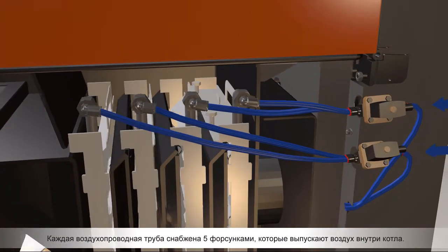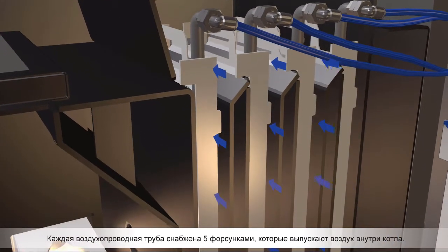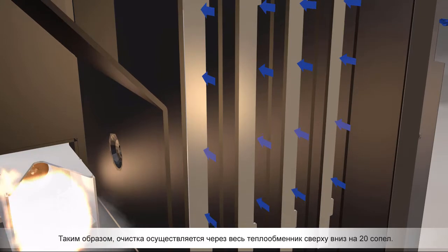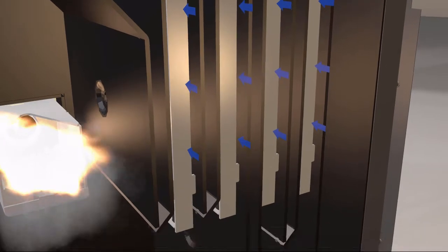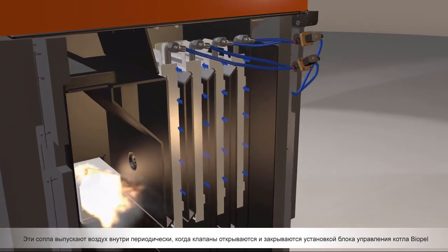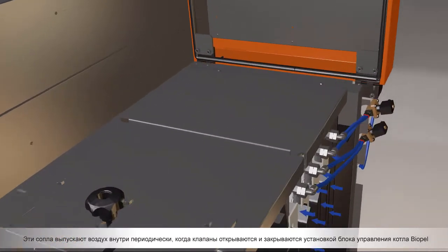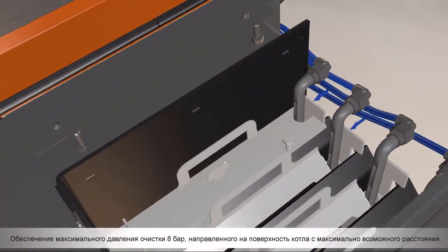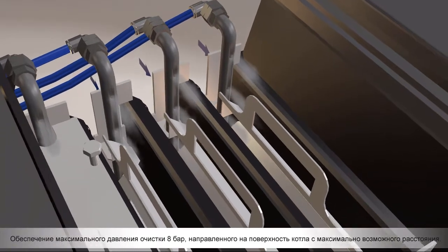Each air pipe is provided with five nozzles which release air inside the boiler. The cleaning is performed throughout the wall heat exchanger from top to bottom by a total of 20 nozzles. These nozzles release air periodically and are opened and closed by the setup of Biopel control unit, providing a maximum cleaning pressure of eight bars directly at the boiler surface from the closest distance possible.